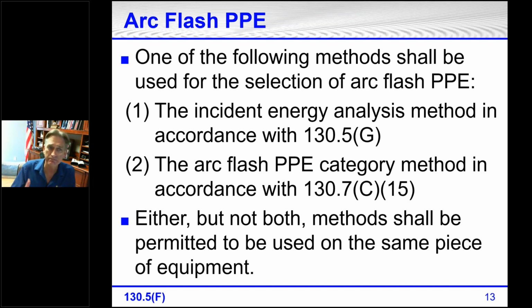There's another method, and it's using the tables in 70E. It is the arc flash PPE category method in accordance with 130.7C15. If you're somewhat familiar with arc flash, with 70E, with personal protective equipment, arc rating, there are 4 categories. Now, be careful that we're not talking about test instruments at this point, but test instruments also have 4 categories. These categories, abbreviated CAT, have nothing to do with each other.